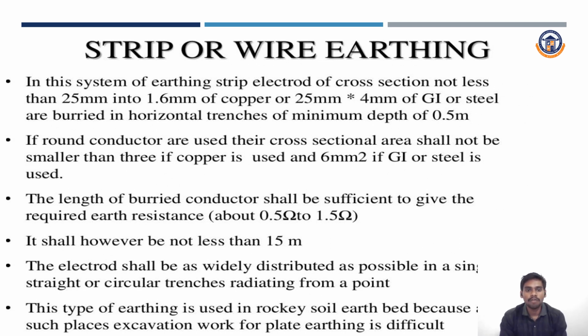Strip or wire earthing. In this system of earthing, a strip electrode of cross section not less than 25 millimeter by 1.6 millimeter of copper, or 25 millimeter by 4 millimeter of galvanized iron or steel, is buried in horizontal trenches of minimum depth of 0.5 meter. If a round conductor is used, the cross-sectional area shall not be smaller than 3 millimeter square if copper is used and 6 millimeter square if galvanized iron or steel is used. The length of buried conductor shall be sufficient to give the required earth resistance of about 0.5 ohm to 1.5 ohms. It shall, however, be not less than 15 meters. The electrodes shall be as widely distributed as possible, in single straight or circular trenches radiating from a point. This type of earthing is used in rocky soil and earthy beds, in places where excavation work for plate earthing is difficult.